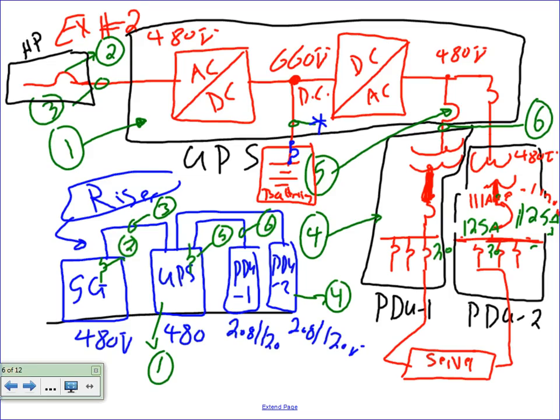So long story short, as far as you're concerned, the PDUs solve the problem of harmonics that's coming out of these servers. These servers are heavy harmonic loads that could screw up your system. So they filter the harmonics right here, the harmonics coming to the server and the harmonics that are reflected back into the system. They have a transformer, and they solve the problem of harmonics by filters and by doubling the neutral. So that's it, really. Other than that, it's a unit. This is what we call a unit substation. Remember how we said unit substation? It's exactly a unit substation, except it's 480 to 208.